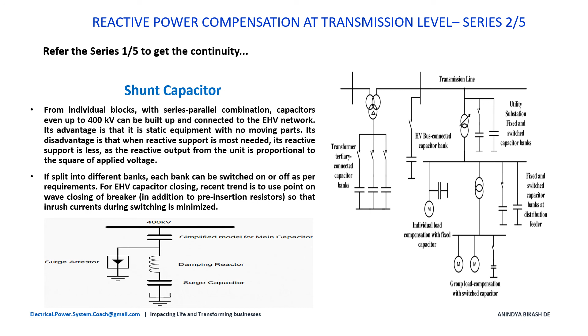Here on the right side, some capacitor banks are shown, how they are used at the transmission level and also at the industrial level. You can verify it. The recent trend is that for EHV capacitor closing, we can use point on wave closing of the circuit breaker so that the inrush current during switching is minimized. You can use the capacitors as fixed shunt as well as switched shunt. In switched shunt, there may be several megavars in blocks that can be switched and configured in a sequential manner.